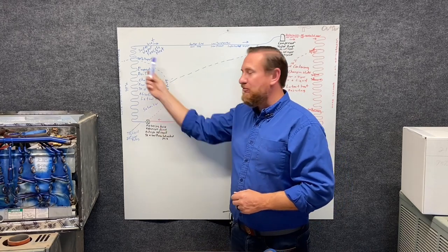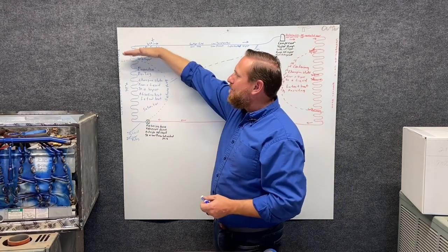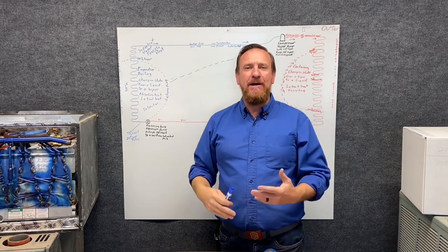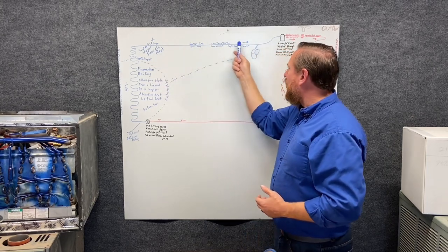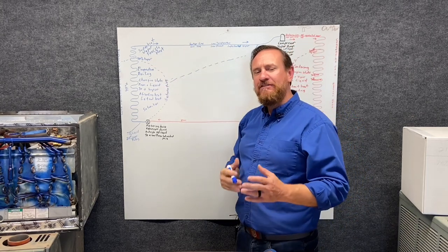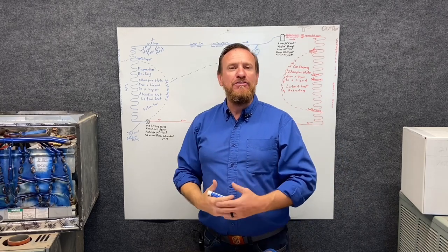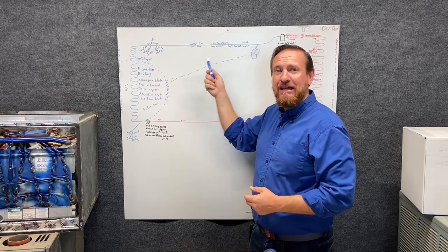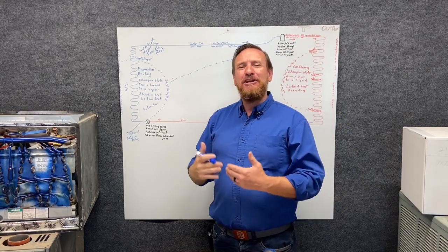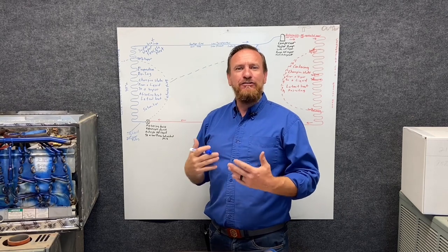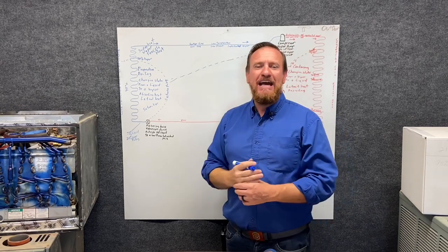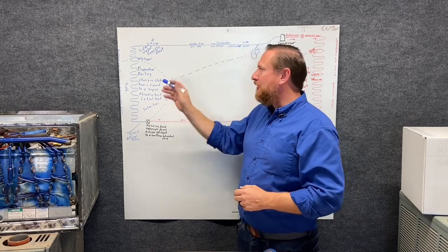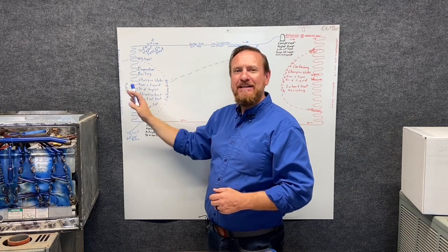So here's saturation, which is latent heat. Superheat's going to add above that, and it's sensible, we can measure it. The amount of sensible heat added to a vapor above saturation. So we're going to be adding heat all the way back to the compressor. And superheat's a very important number. I want to always know that I have superheated vapor because this is a vapor pump. If I have saturation, I'm going to have some kind of liquid getting in, and we don't want liquid. So we want to make sure that we always have some kind of superheated vapor. A compressor, you never want to have anything less than 5 degrees of superheat to protect the compressor from any liquid. But superheat is a very important number because it tells us what's happening in the evaporator.